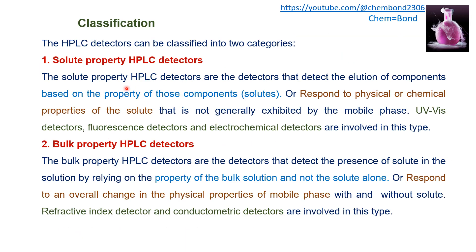HPLC detectors are classified into two categories: solute property HPLC detectors and bulk property HPLC detectors. In solute property HPLC detectors, the response depends upon the solute and not on the mobile phase — it measures a property of the solute that is not exhibited by the mobile phase. These detectors detect the elution of components based on the physical or chemical properties of those solutes. UV-visible detectors, fluorescence detectors, and electrochemical detectors are included in this type.